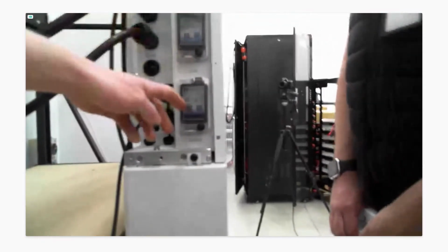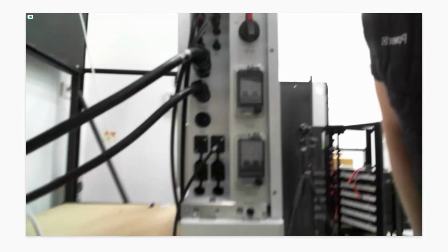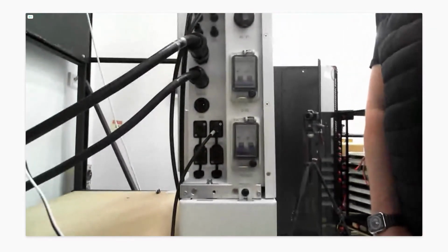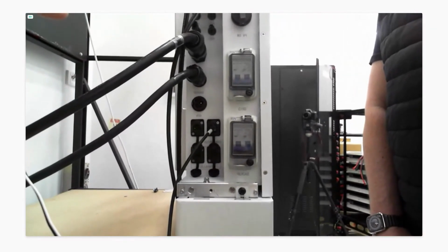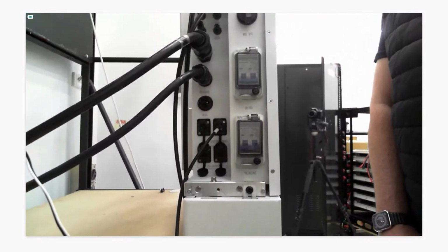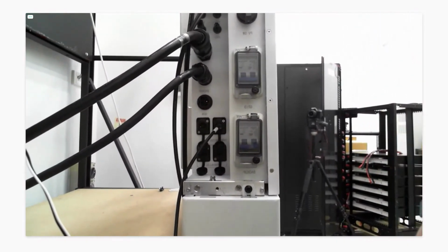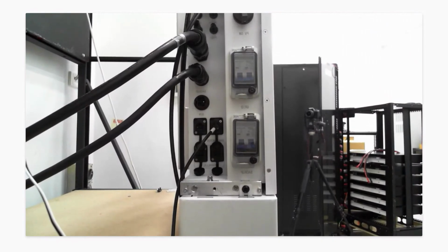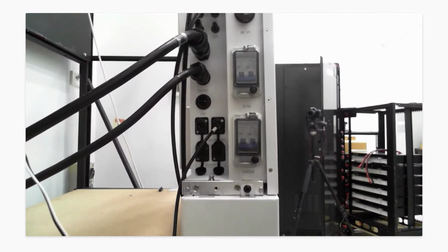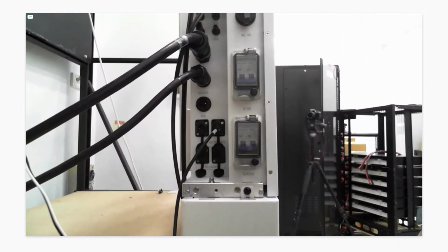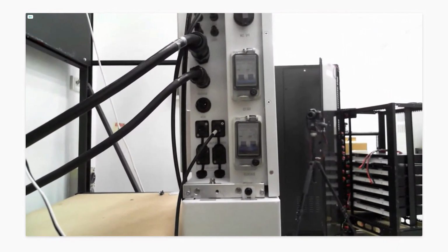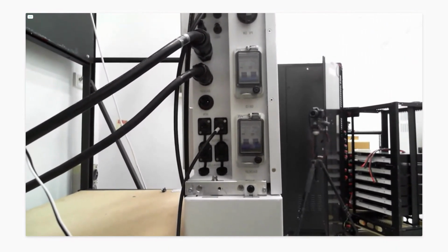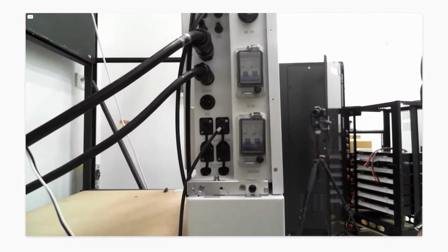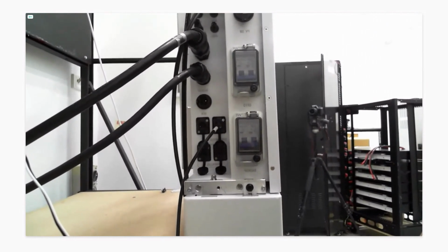And then these circuit breakers here - does this mean that you don't need another subboard, or is that a bit up in the air? I wouldn't say necessarily a subboard, but it might allow us to sidestep the need for an additional AC isolator right next to the system, which is far away from the meter box. But like we said at the start of the video, this might be a great area for installers to check specifically in their region or with their inspector.